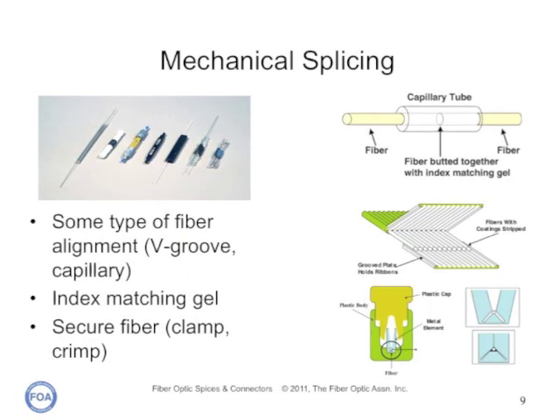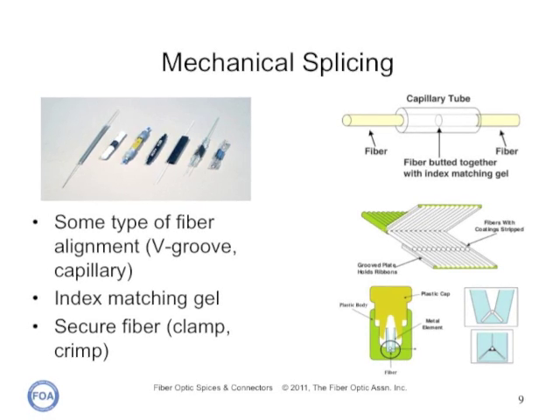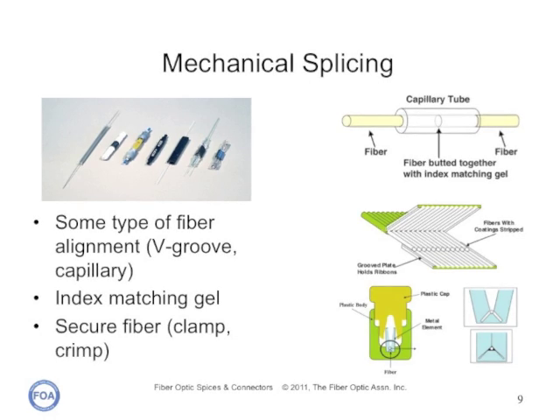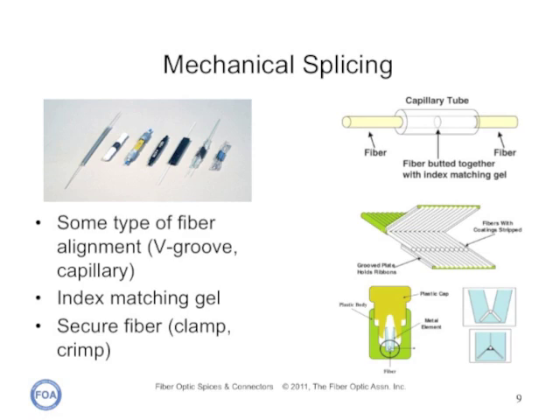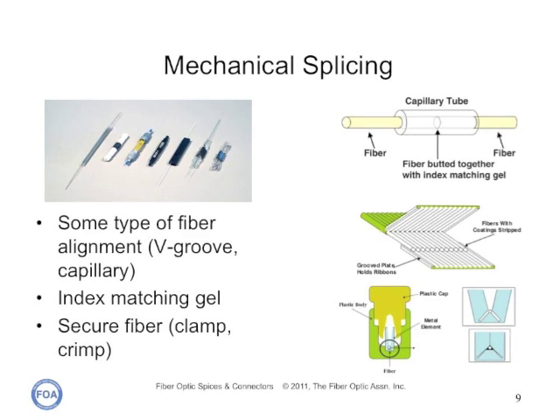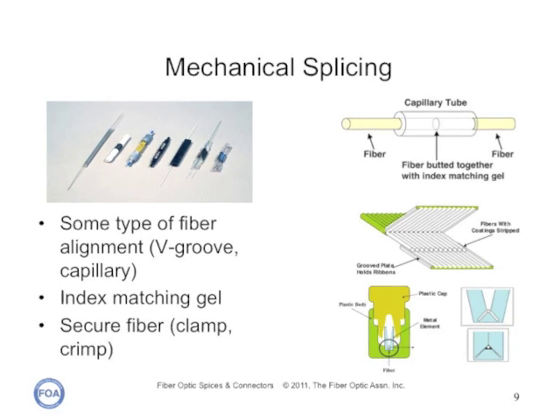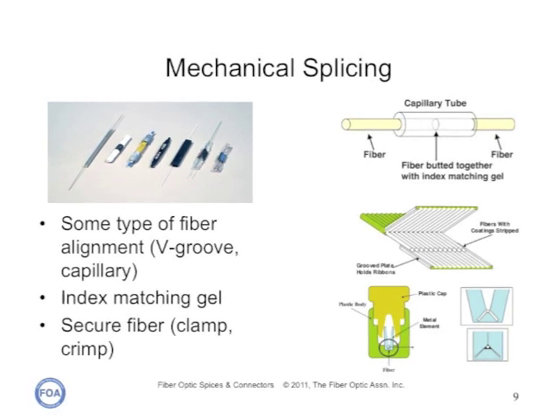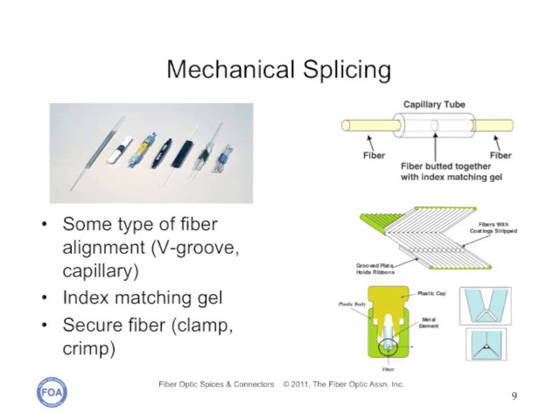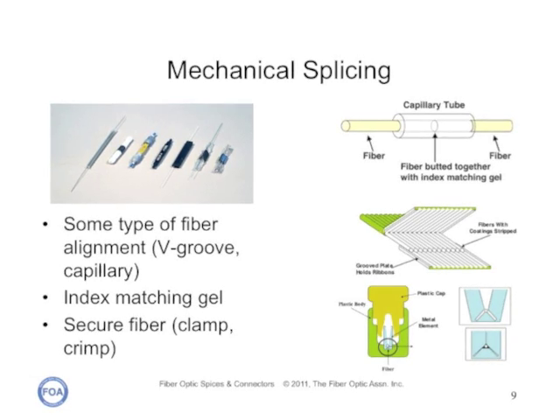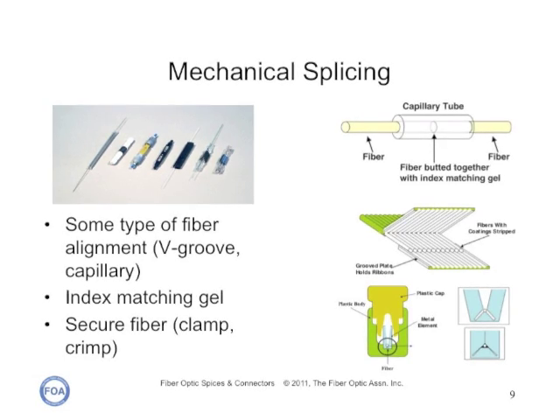Mechanical splices use some type of fiber alignment, typically a V-groove or a capillary, and index matching gel to reduce the reflectance. The fibers are secured by crimping, either with a clamp or a crimp, to hold them in place. Fusion splicing gives lower splice loss because of the fusion of the two fibers in the electric arc. Mechanical splices tend to cost more per splice, because the splices themselves are complex mechanical devices.